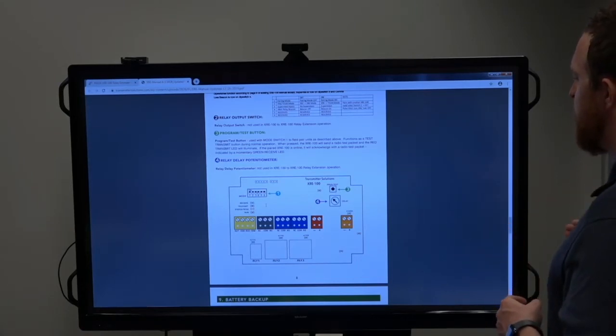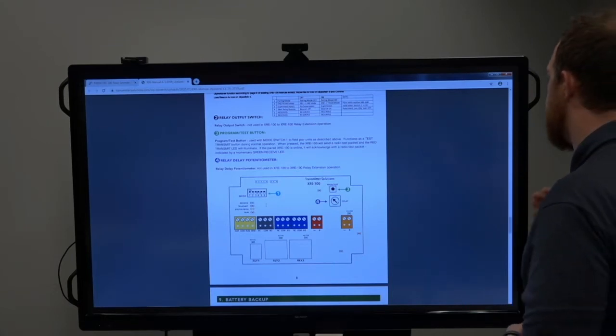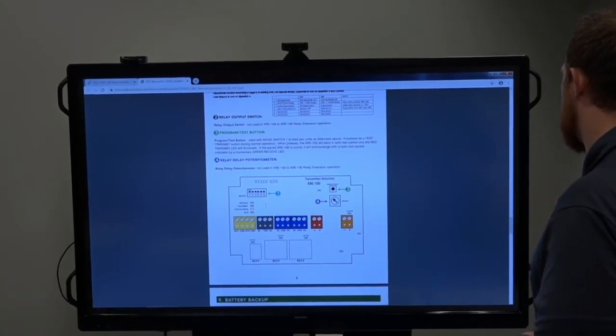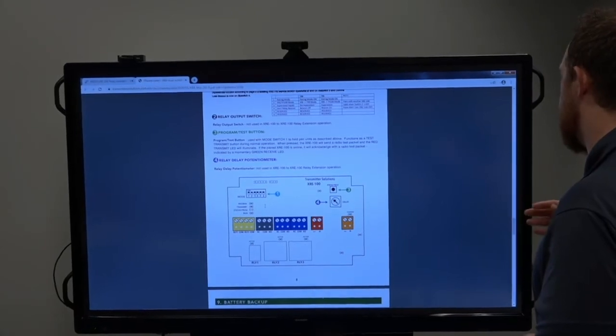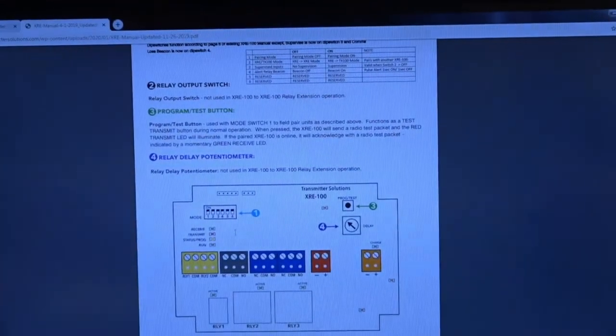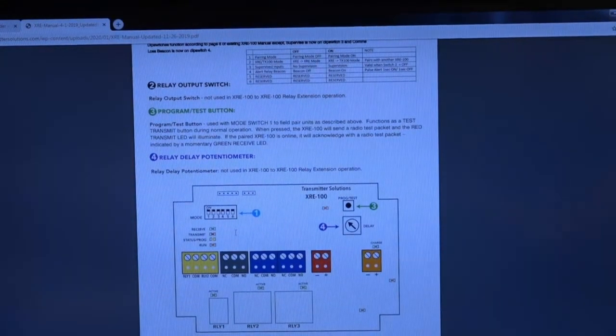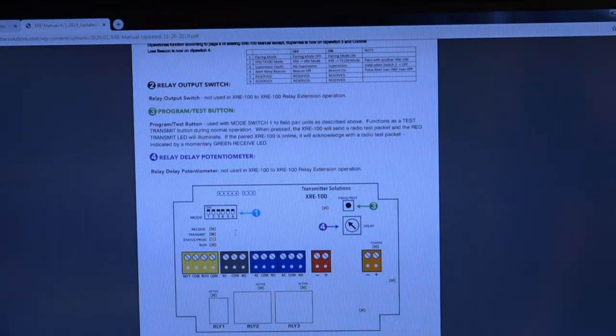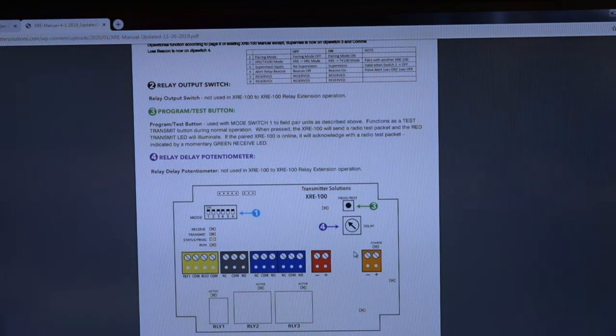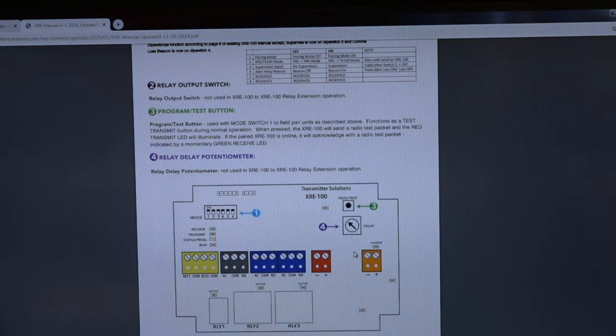DIP switches two, three, four, five, and six: three is used if you're using the alert relay. Four is used for another feature of the alert relay. None of the rest are used, and the potentiometer right under the program test button is not used when you're using the setup we're talking about today, XRE to XRE. That is used if you're using our handheld transmitter to adjust the relay time.